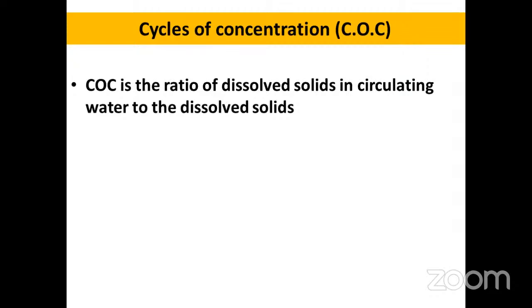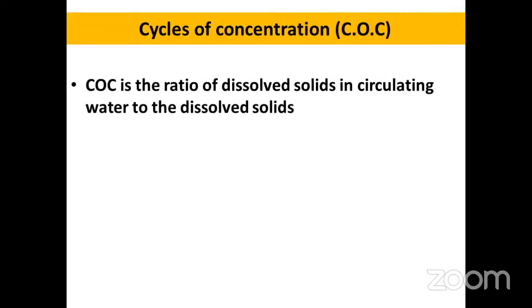COC is the ratio of dissolved solids in circulating water to the dissolved solids in the makeup water, that is, fresh water. Makeup water, in case of Metro, is Kaveri water. In case of the new upcoming power plants, it is fresh sea water.